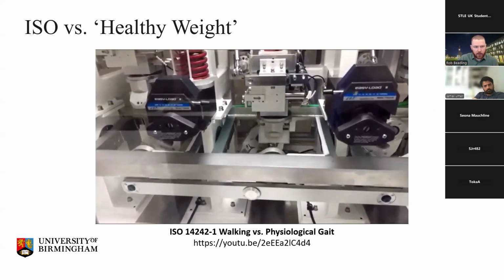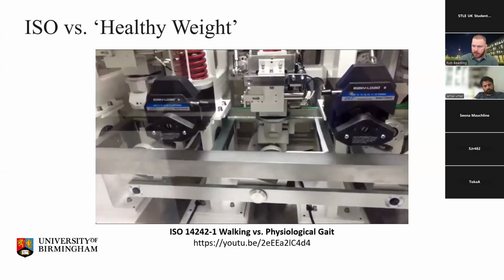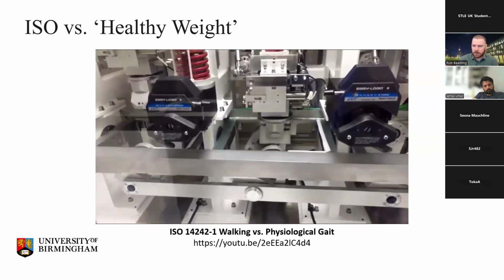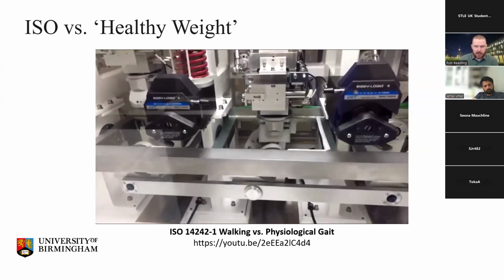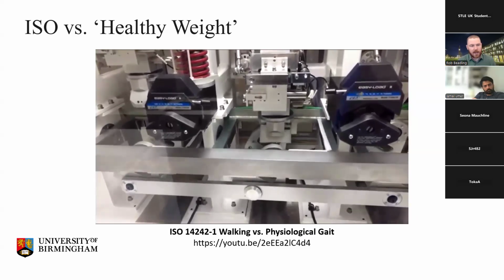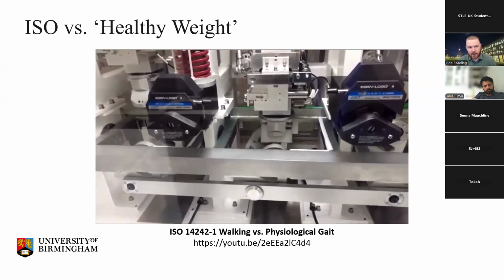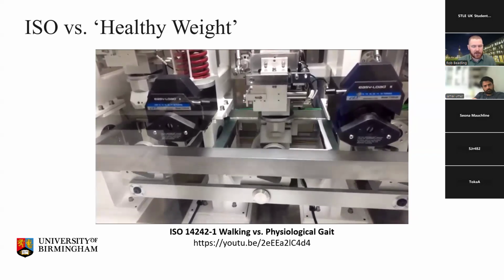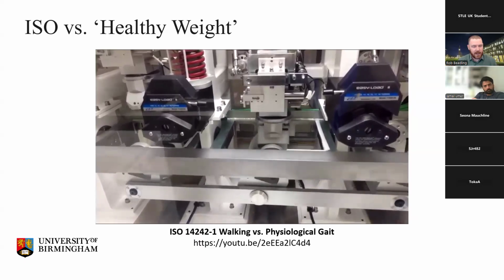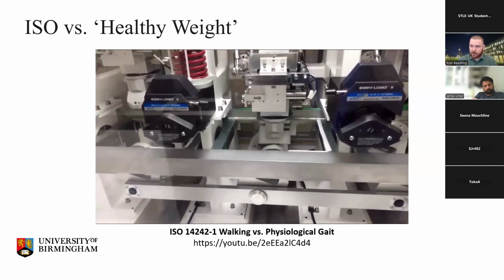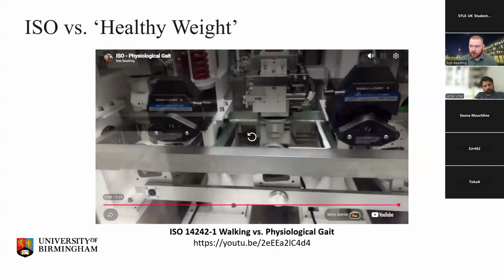Fairly benign sine waves, and then it switches into that kinematic physiological gait. And hopefully you can hear the difference in those profiles running. You get an ear for these simulators when you're running them for a long time in terms of how they're supposed to sound. And yeah, just the kinematics, the severity of just a walking profile is very different from what we test these devices under.